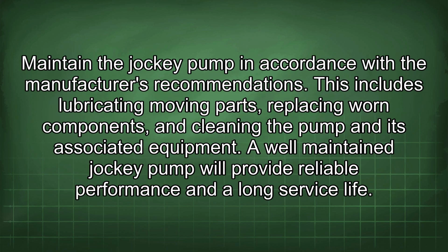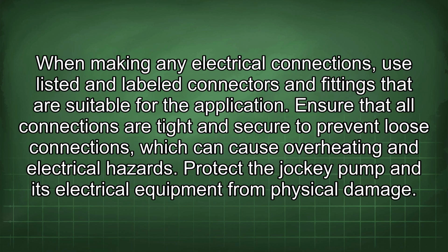Maintain the jockey pump in accordance with the manufacturer's recommendations. This includes lubricating moving parts, replacing worn components, and cleaning the pump and its associated equipment. A well-maintained jockey pump will provide reliable performance and a long service life. When making any electrical connections, use listed and labeled connectors and fittings that are suitable for the application.